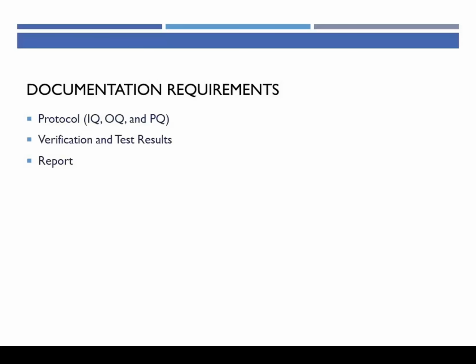Then you're going to go out and do the testing, and provide verification, the proof that you did all of the testing. So you'll show all your data points and your test results. You're going to analyze that data, and then write a report with your conclusions that say whether or not you met your predetermined specifications, whether or not you passed or failed your validation.